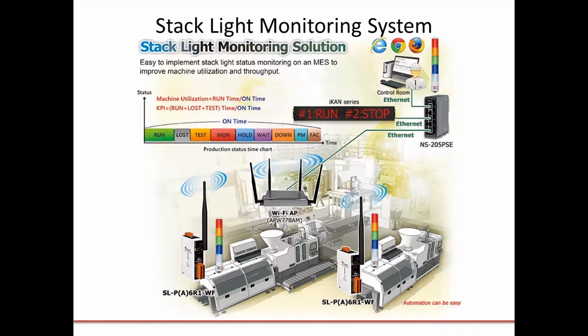This example is using two of our newest products, the SL-P6R1-WF and the SL-PA6R1-WF. These are our Wi-Fi stack light monitoring modules. The first, the P6, is for DC-powered stack lights, and the second, the PA6, is for AC-powered stack lights. Otherwise, they're the same module. Both provide 6 channels digital input and 1 relay output. They have Wi-Fi, Ethernet, and RS-485 interfaces.